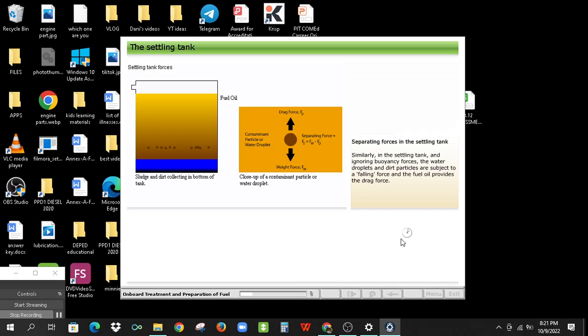Similarly, in the settling tank, and ignoring buoyancy forces, the water droplets and dirt particles are subject to a falling force, and the fuel oil provides the drag force. The size of the drag force is determined by the viscosity and density of the fuel and the surface area of the particle. At increased temperature, the density and viscosity of the fuel oil decreases, and therefore the drag force reduces.